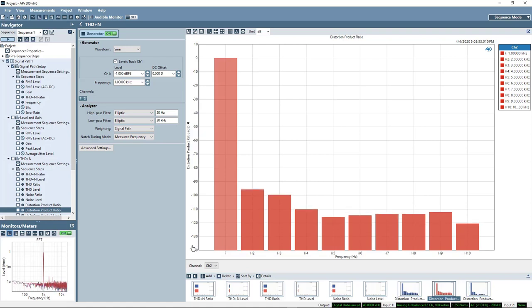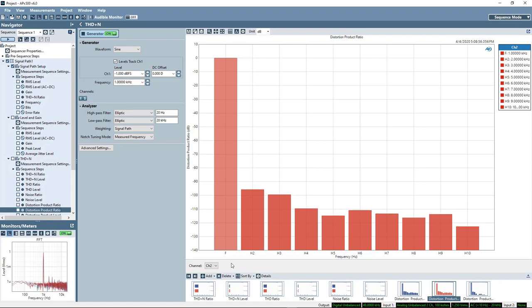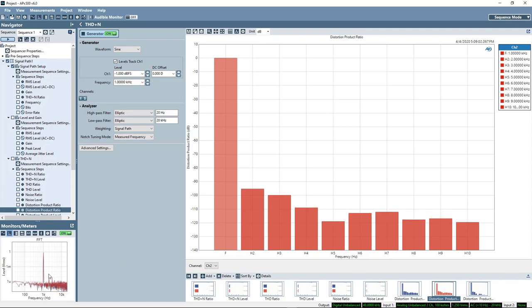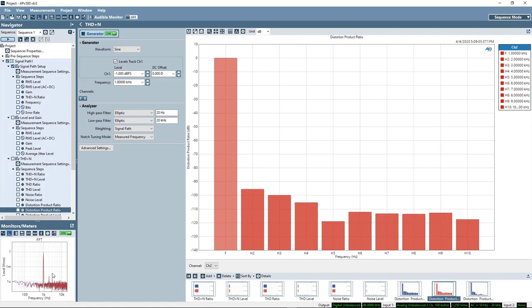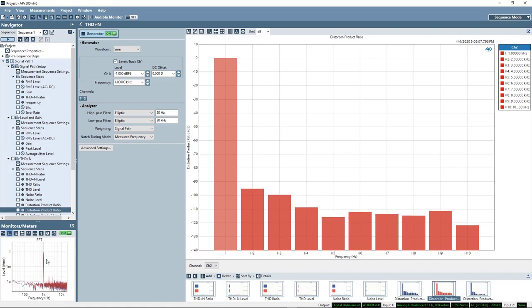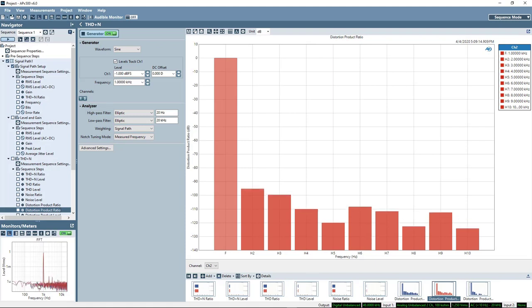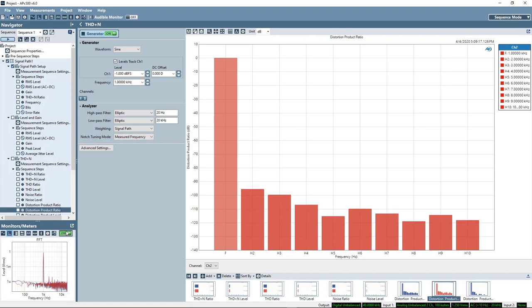And I can drag that over. And I'll set this second instance of the graph to look at the second channel. Of course this is all possible because the measurement is being made in the frequency domain. As you can see down here in the input signal monitor where we're performing an FFT of the live signal coming back from the device, we can look at the output and easily discern the fundamental products, the distortion products, and the noise of the device.